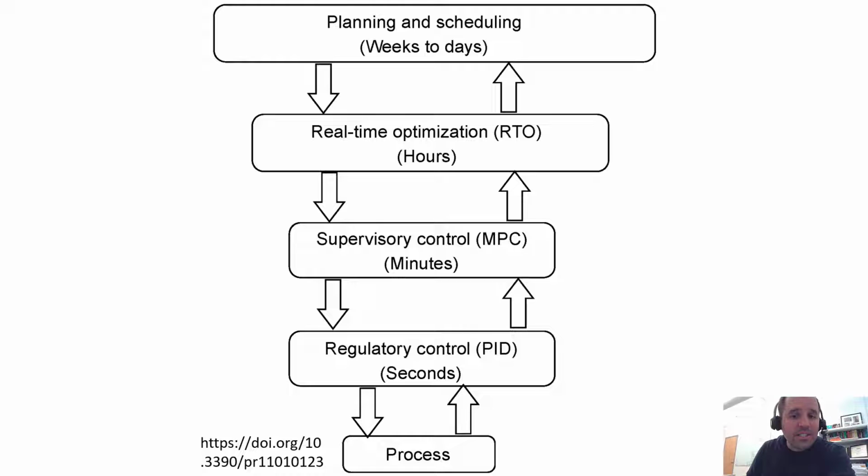And MPC is typically a multivariable control. So rather than having one actuator linked to one controlled variable, you might have multiple actuators linked to multiple control variables. Above that layer is something called real-time optimization. Similar to model predictive control, real-time optimization allows you to build a mathematical model of your system, and then you solve that mathematical model typically for optimum economic conditions for your plant.